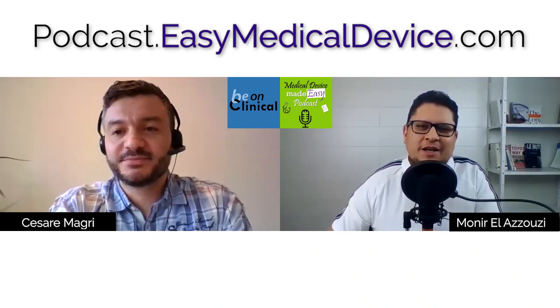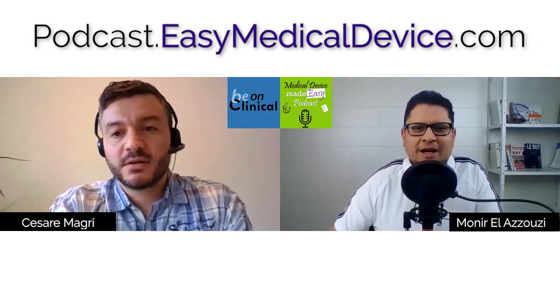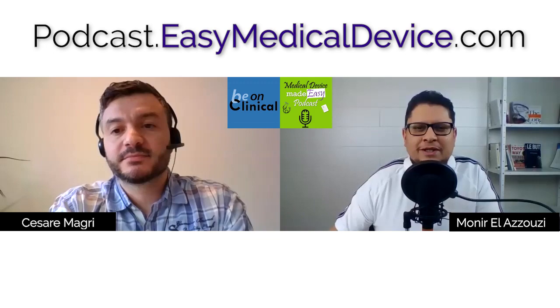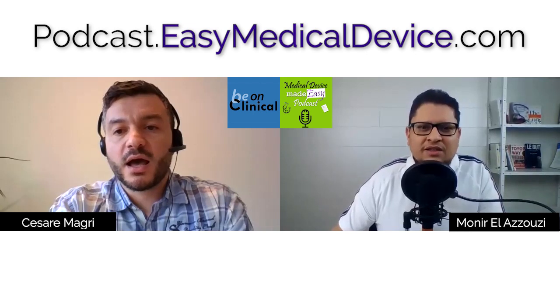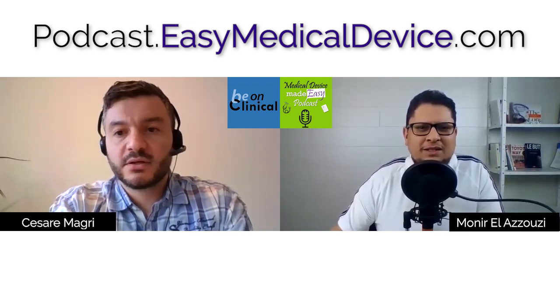Yeah, so some of the mistakes I also see is people putting in claims that are not really true, but which change the classification of the device to a higher class, or even from a medical device to a drug, because there are some substances inside that can maybe be considered a drug. So I think it's important to stress: be careful of what you are writing, because it can still be a medical device but now in a higher class, or it can not be a medical device anymore just because you added this thing. Is that something you have already seen?